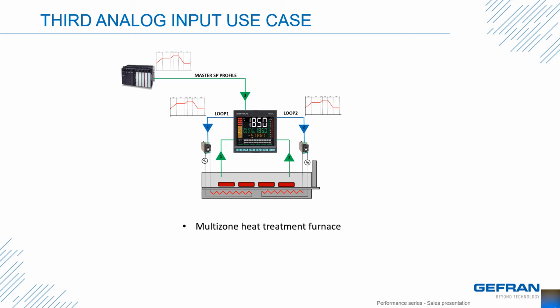Or maybe temperatures need to change based on the speed of a conveyor belt or some other process. When I think of remote set points, maybe this is a multiple zone platen press, downstream equipment, composites, or packaging applications. What if the ramp soak was turned off and this was a conveyor or a continuous process? Keep in mind the third input as a remote set point would be used in the concept of cascade control. With the weekly clock and timers, math and logic functions, this could lend itself to some pretty interesting applications and solutions.